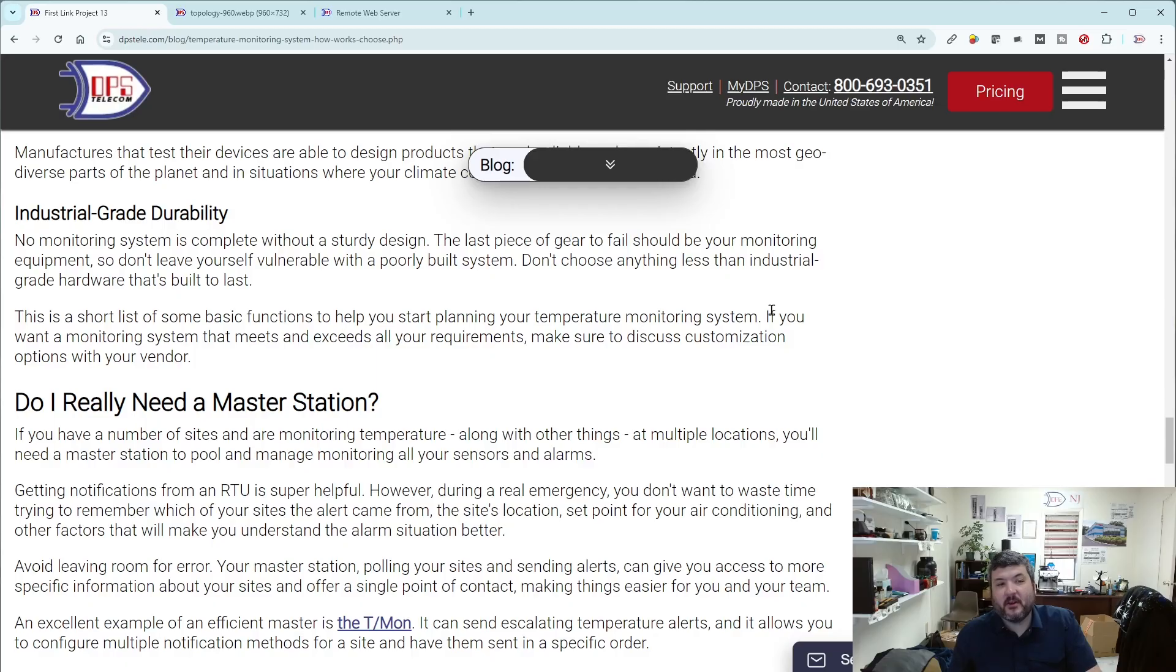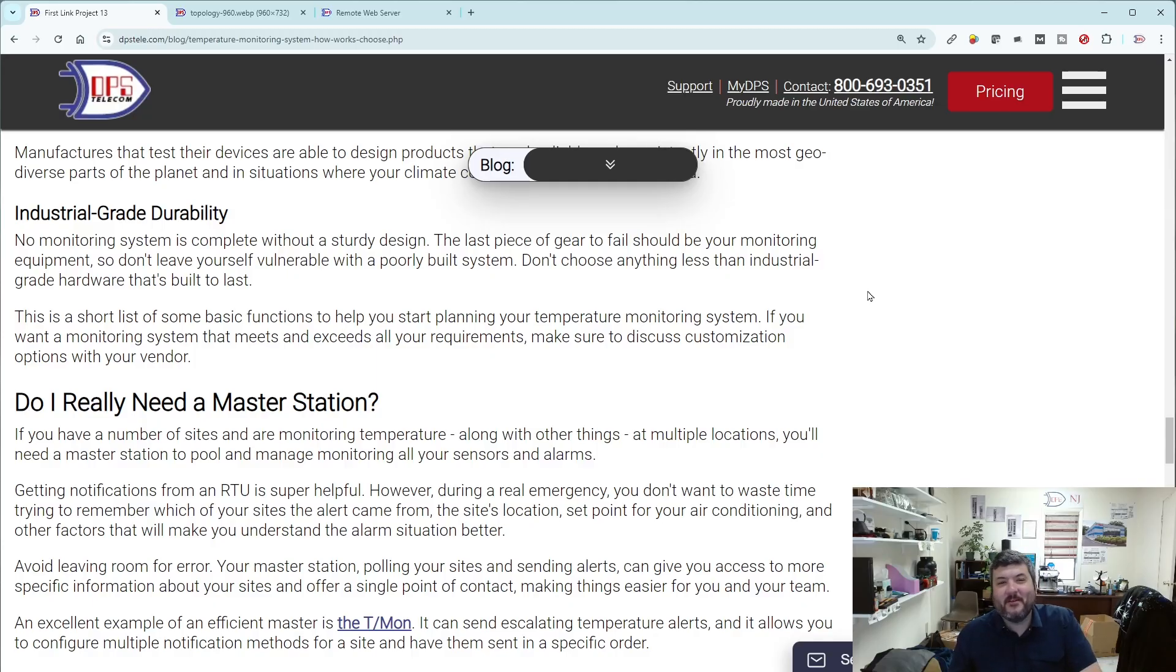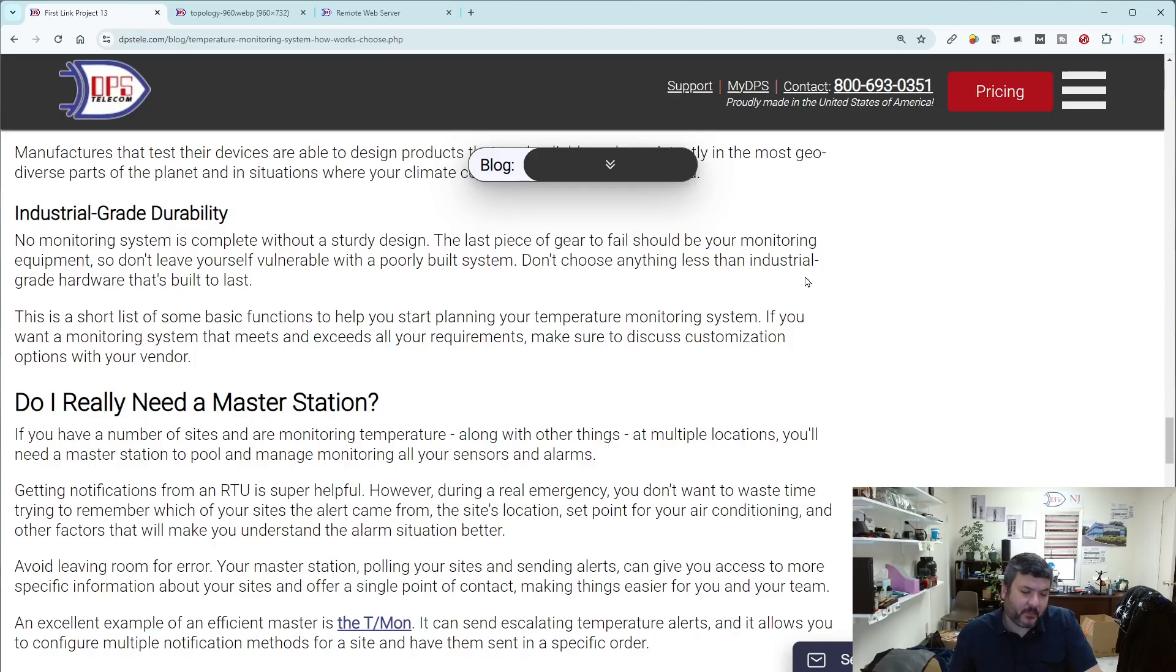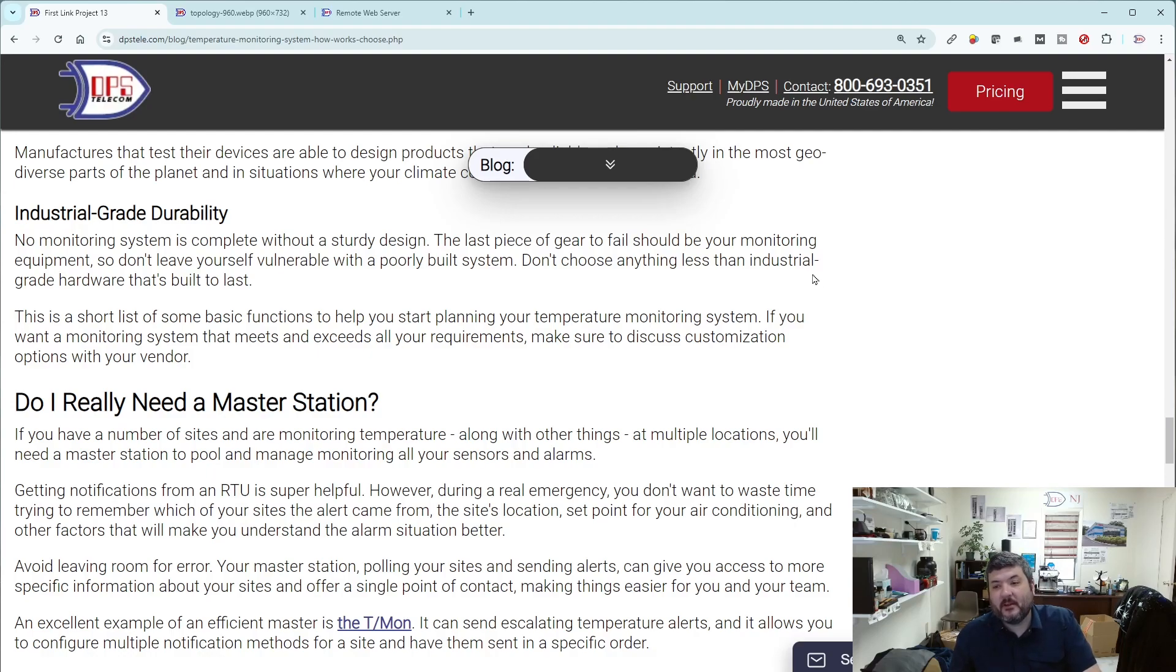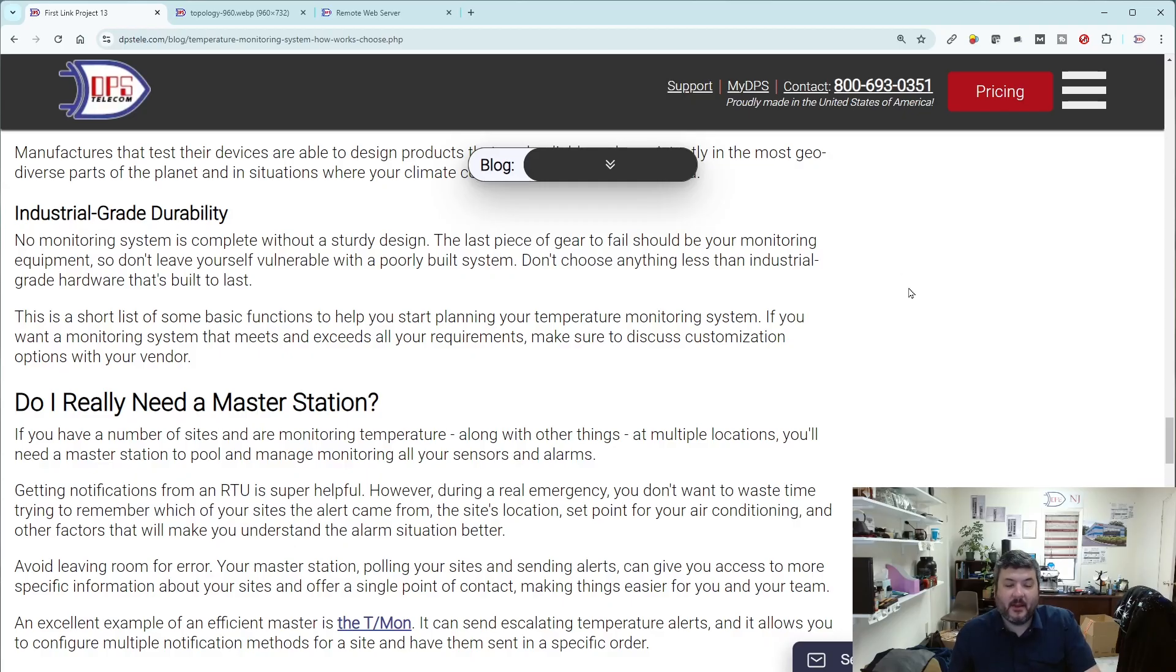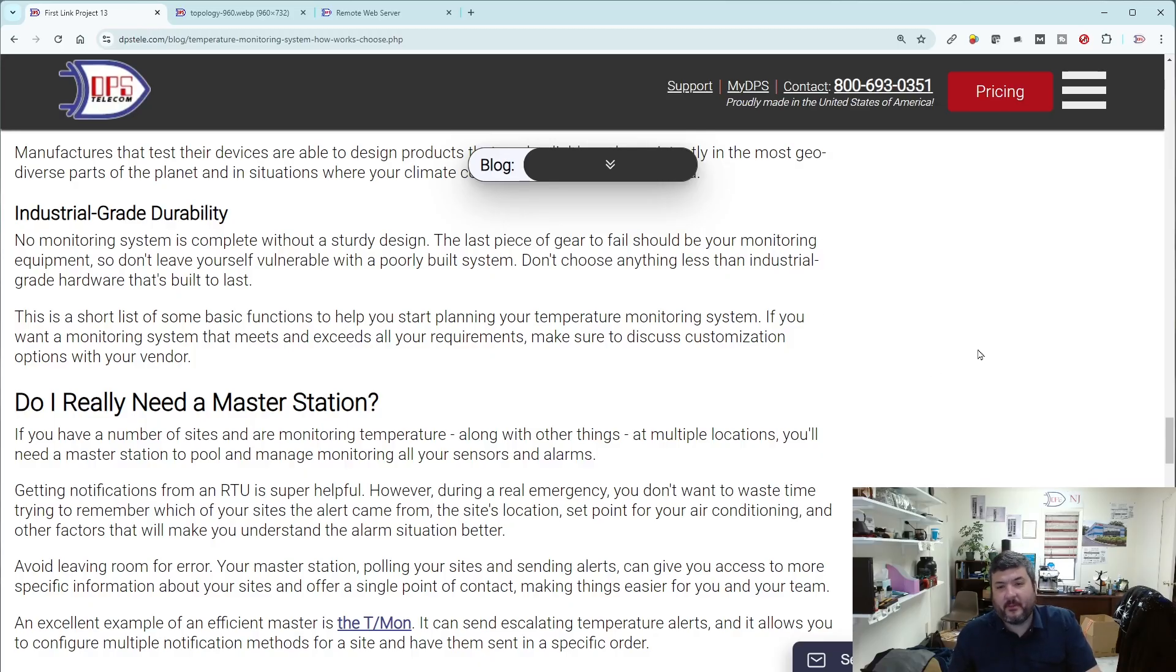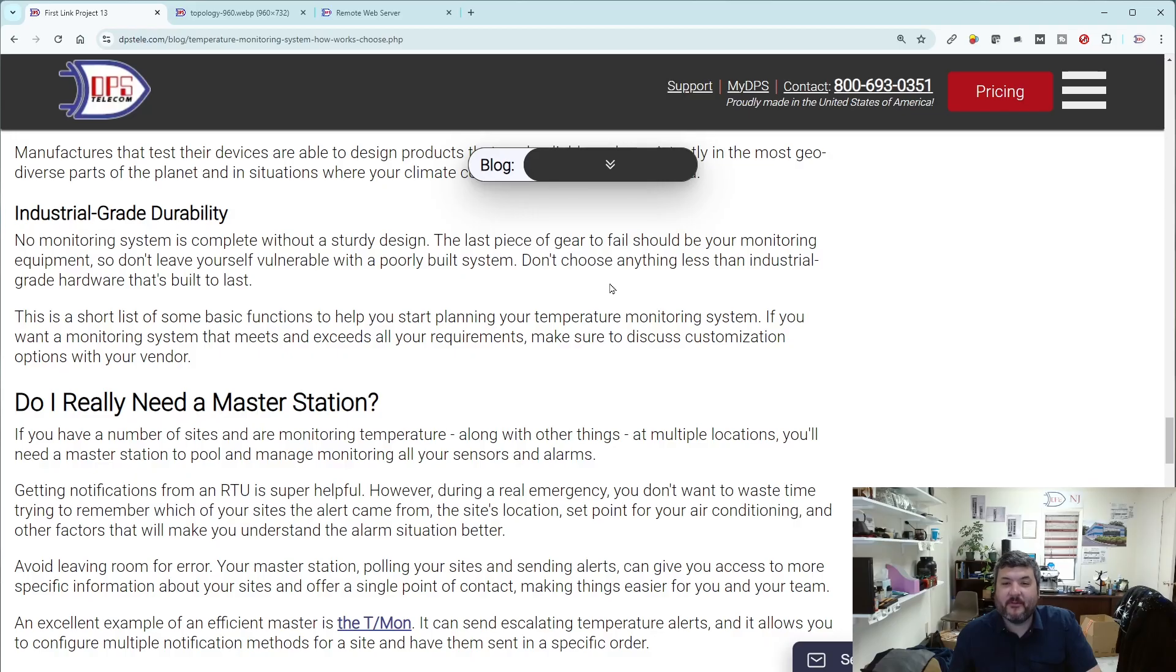Not only should your RTU be able to survive your temperature extremes so it can keep doing its monitoring job, but in general look for manufacturers who have gear that's been installed for many decades and have probably improved their designs. At DPS we have engineering and manufacturing on site. One thing you'll notice on the bottom of NetGuardians - why do they use 25 or 30 screws to hold the circuit board into place? You really need about five mechanically. That has to do with EMI reduction or electromagnetic interference reduction. If you have a part that's noisy or susceptible to outside interference, if you have a ground attachment really close to it, which is that the screws hold the circuit board into the metal and ground it out, that is a tool we use to reduce our susceptibility to outside interference. Little details like that can go a long way in some of the unfortunately rough environments that our equipment has to survive in.